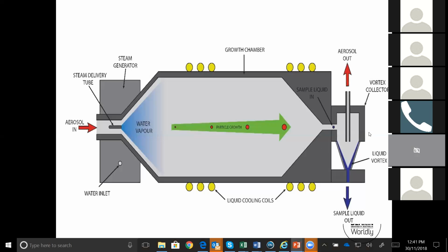It was really hard. The surface finish, sample liquid temperature, aerosol flow rates, everything plays a role in determining the vortex formation. We were tuning these parameters for like 3 years, I think. And this large range of parameters makes prediction of vortex formation difficult, necessitating a design which allows for a visual confirmation of the vortex.